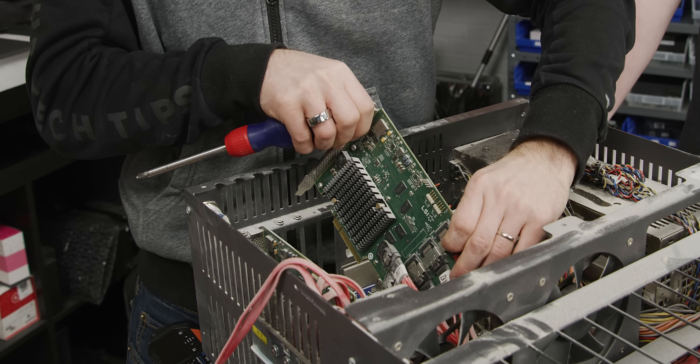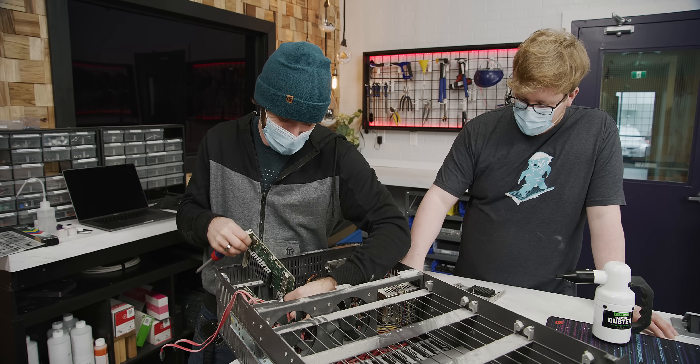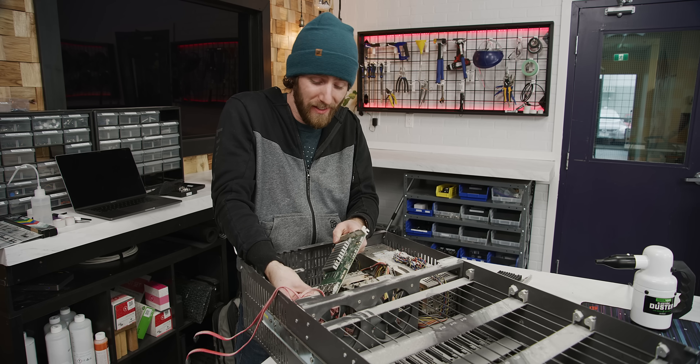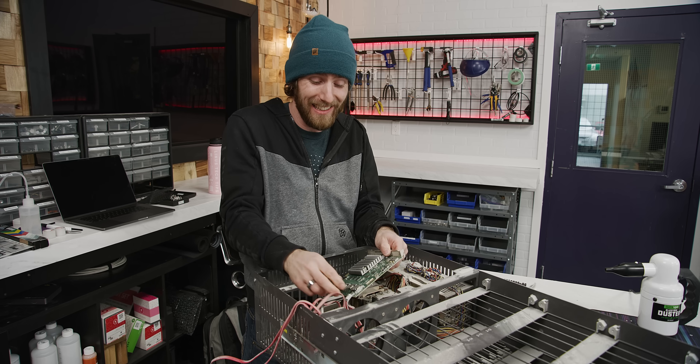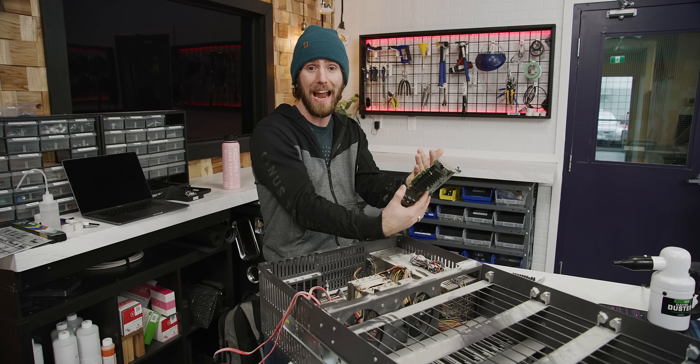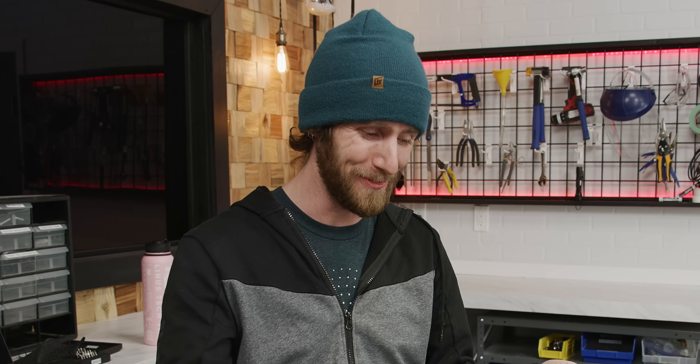The vertical parts aren't that bad - that's how you can tell that it was falling dust. Just a little bit of drywall. For those of you wondering what the heck went wrong here: part of it is that this thing's been sitting around for a couple of years, but the other part is that it was accidentally left in a rack that was inside a construction zone. The construction workers very thoughtfully built a box around the rack thinking they were protecting the delicate equipment inside - they didn't understand that having a big opening in the top meant the dust would go right in. Anyway, we can fix it. Hopefully.